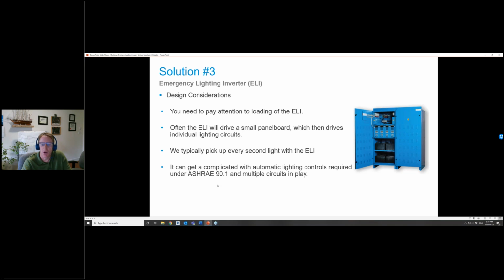And just as a side note, if you're dealing with automatic lighting controls required under ASHRAE 90.1, and you have these multiple lighting circuits in play, things can get a little tricky. So we have some solutions for that involving multiple power packs that switch simultaneously both circuits using a common set of sensors, but that's a little bit beyond the scope of what we're talking about today, but just something to keep in mind.